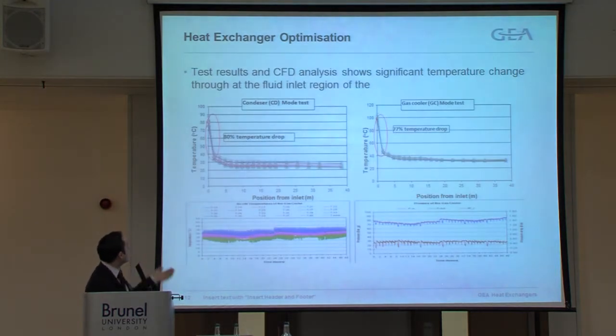This is a small selection of the test results. The gas cooler's been running for about 18 months, so there's too many test results to possibly go through them all. But it can be seen that in condenser mode, you would get a significant amount of de-superheating occurring as the fluid's entering the gas cooler. And in gas cooler mode, you can see that you're getting up to 80% temperature drop within the first few meters of the coil. So on the x-axis here, this is the meters from the inlet, the distance from the inlet of each circuit going through the coil, and the y-axis is the temperature drop.